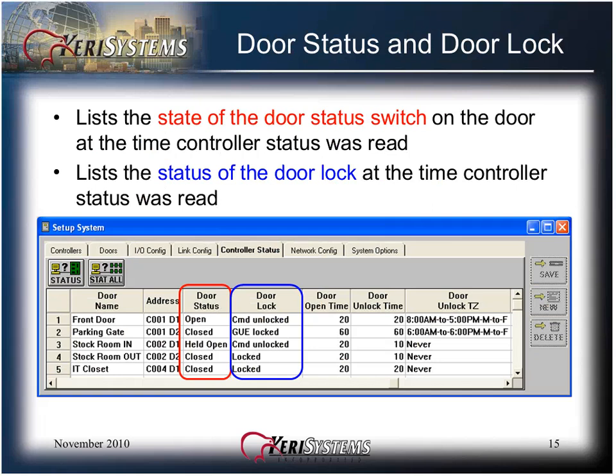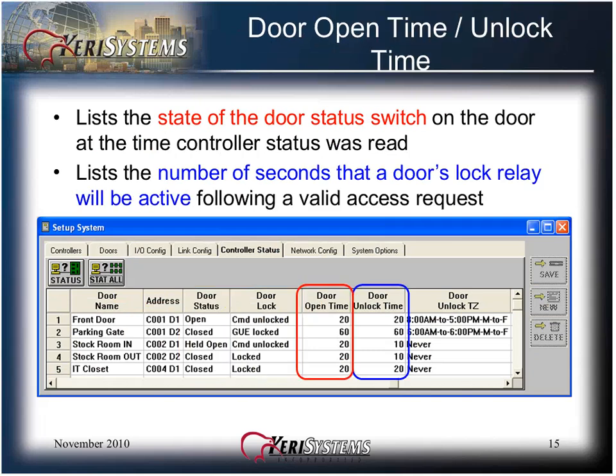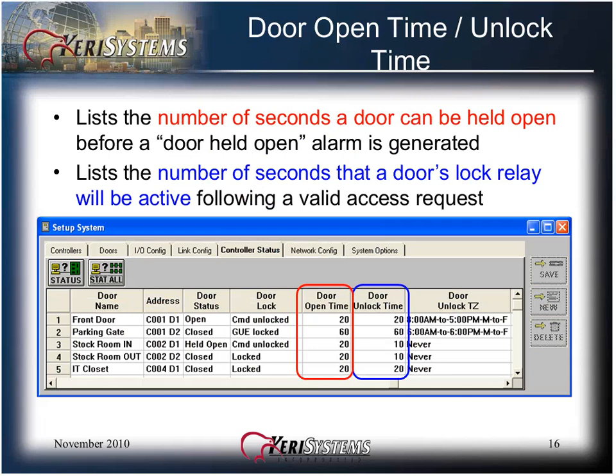The door status and door lock columns indicate the state of the door status switch and the door lock at the time the controller status was read. The open door time lists the number of seconds a door can be held open before a door held open alarm is generated. And the door unlock time lists the number of seconds that a door's lock relay will be active following a valid access request. This information is reflective of what was programmed in the doors tab of setup system.